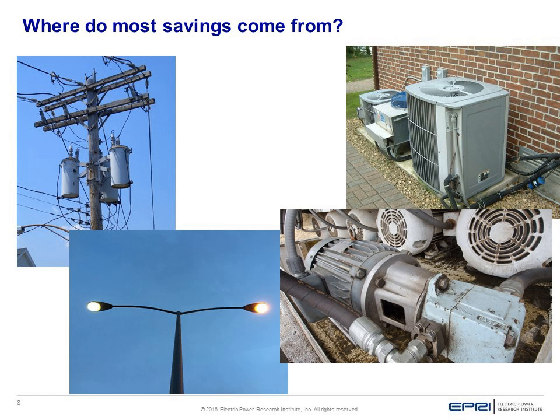As I said earlier, when you reduce voltage to equipment, a lot of it draws less electricity. Some of the biggest examples are shown on the screen. Lighting is a huge component of a conservation voltage reduction program — when you reduce voltage to many lighting fixtures, you'll reduce consumption. Now with lighting, you will also lower the light output.